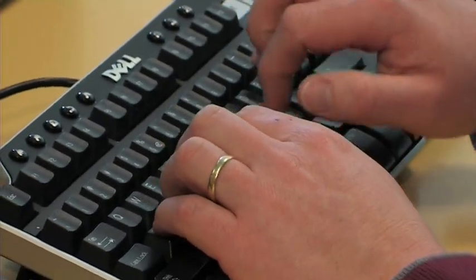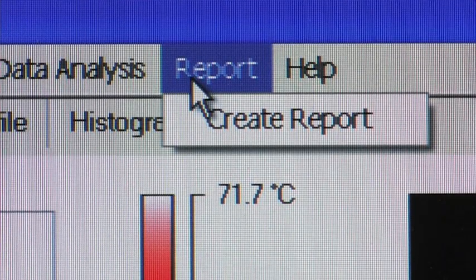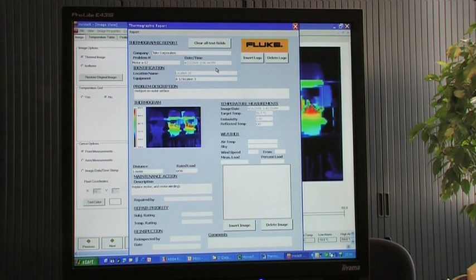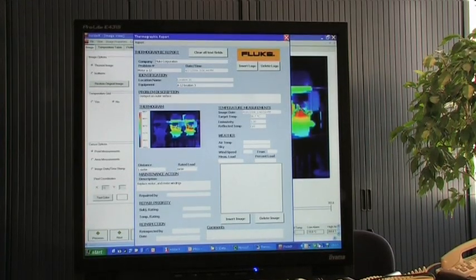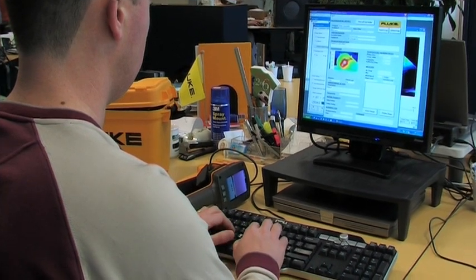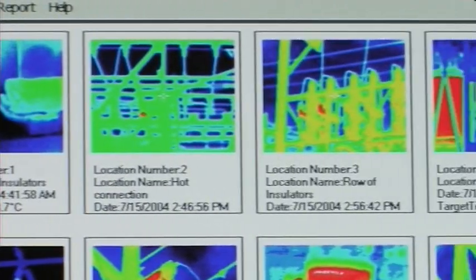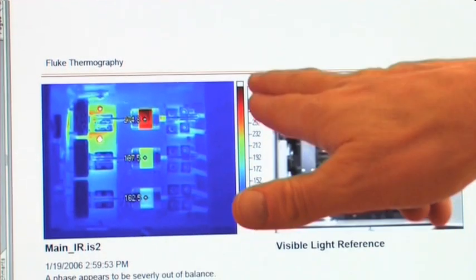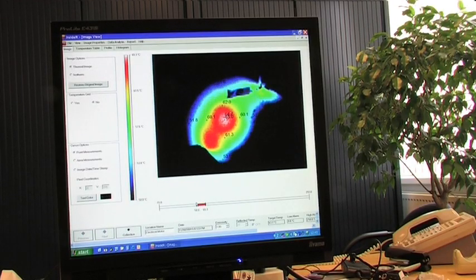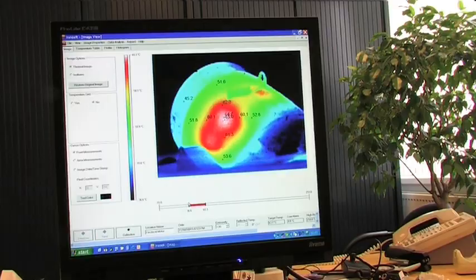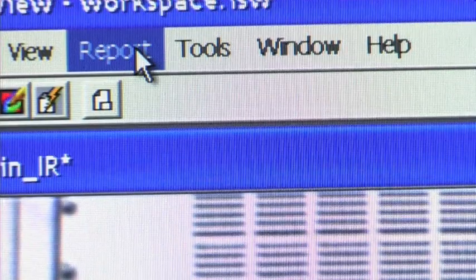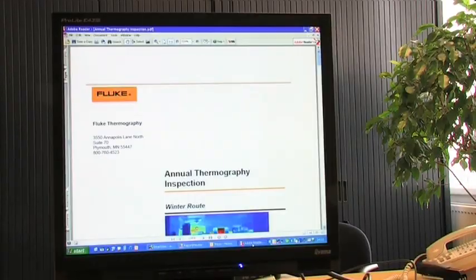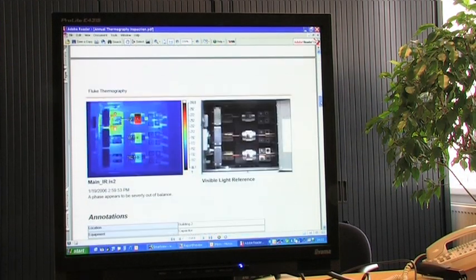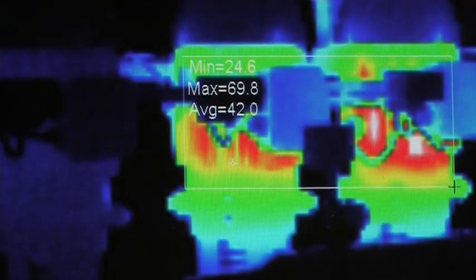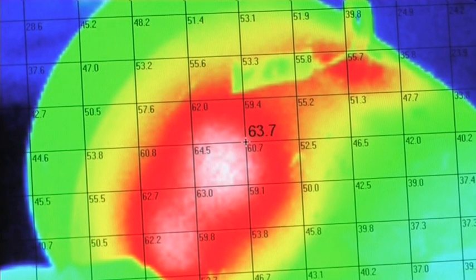The Fluke thermal imagers are supplied with reporting and analysis software. This software allows you to set up a predictive maintenance program. Images taken during regular inspections are easily compared to previous ones, helping to identify potential problems before they cause failure. A detailed analysis of the image using dedicated software can also include changing the image parameters to zoom in to potential problem areas. The software's report generator makes it easy to communicate findings and repair instructions to the maintenance department. Fluke software can be loaded on as many computers as you need, as there are no additional licensing fees.